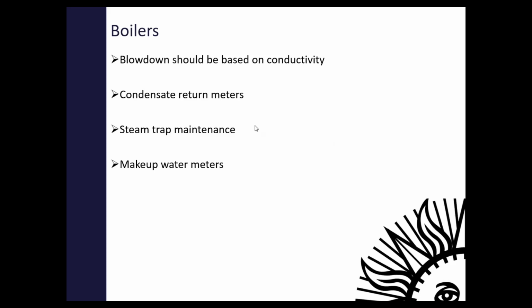Condensate coming back to your boilers is a lot more important though, because this contains not only water used in your steam, but also the energy used to generate the steam. So you can use this water instead of cold makeup water, and then your boiler will do less work, and of course you're saving water because you're not introducing that additional water to your boiler. And that comes along with steam trap maintenance. If you have a steam trap that is either blowing through, plugged up, or leaking, that's a source of wasted water right there. If it's a source of wasted steam, it's a source of wasted water as well.